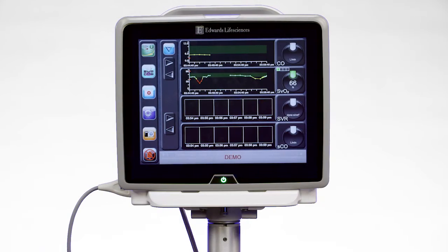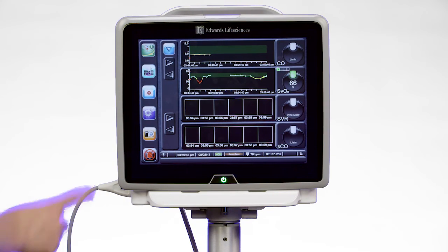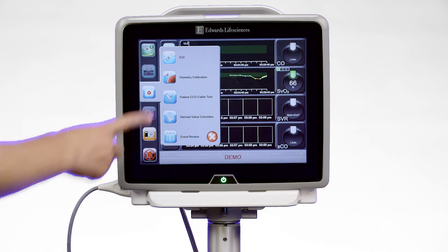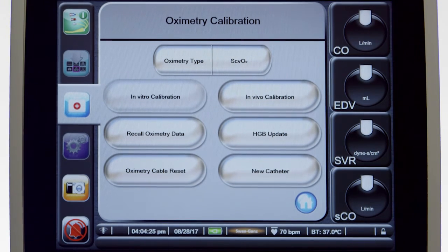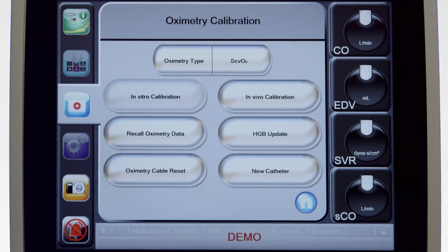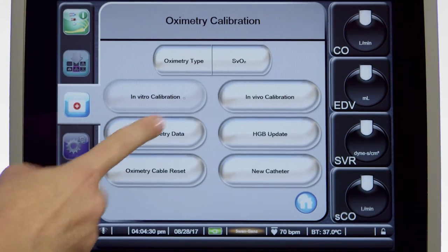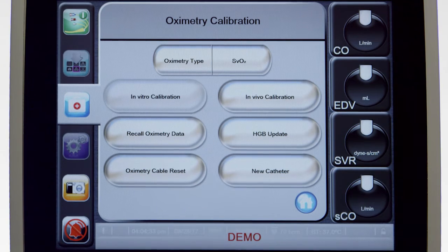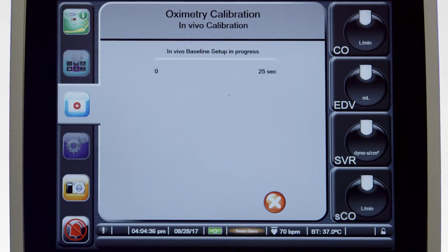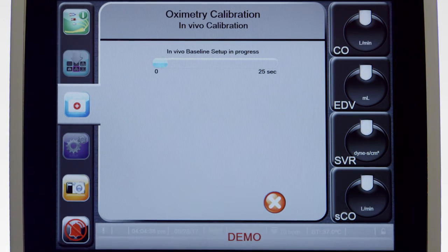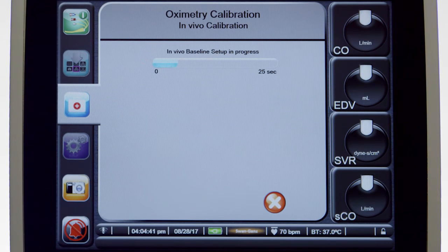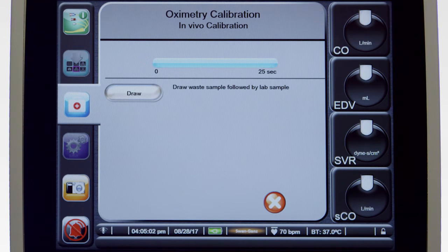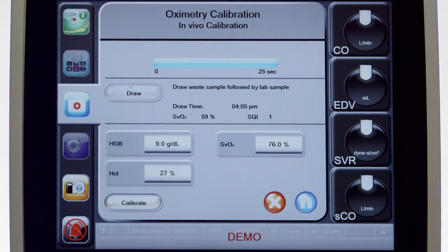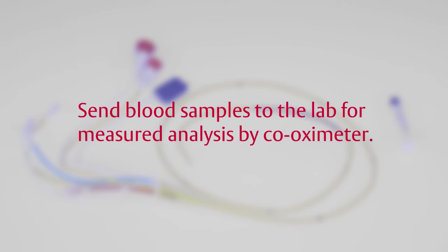To start the in vivo calibration, touch the Clinical Actions button and then touch the Oximetry calibration icon. At the top of the Oximetry calibration screen, select SCVO2 or SVO2 for the oximetry type. Touch the In Vivo Calibration button. It may take up to 25 seconds to complete the calibration. If the calibration is successful, you will be prompted to draw a waste blood sample followed by a lab sample. Touch Draw, and then draw the blood sample. Send the blood samples to the lab for measured analysis by co-oximeter.